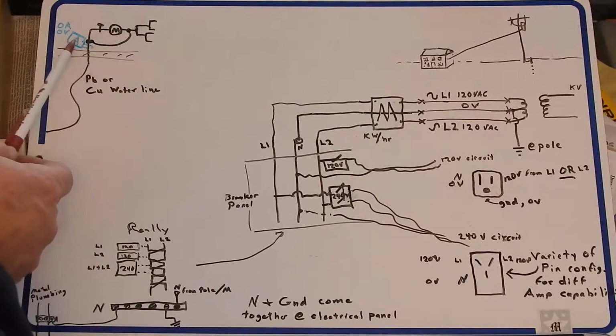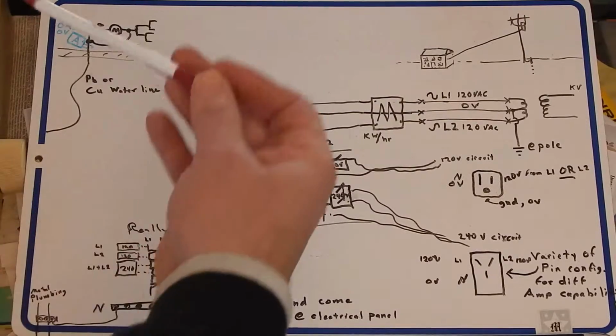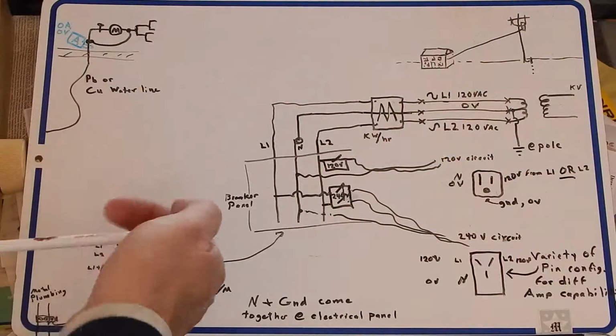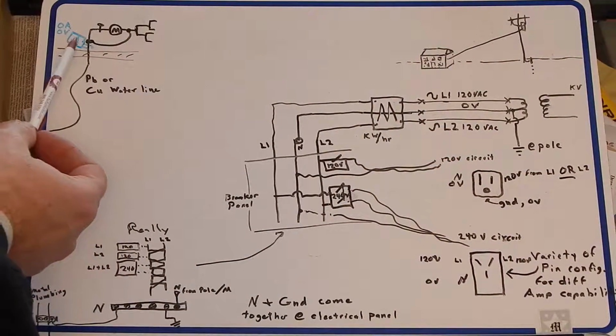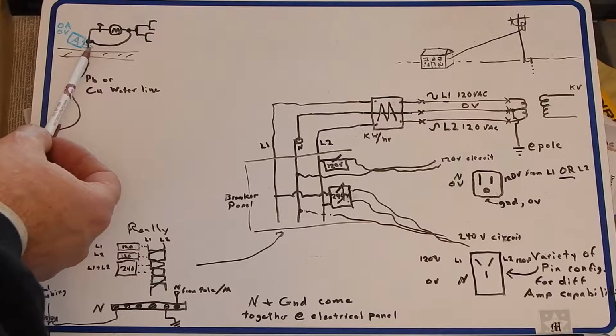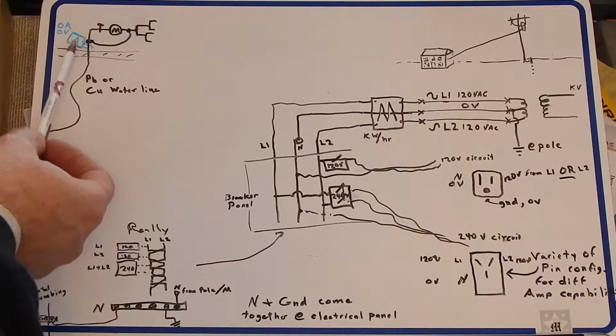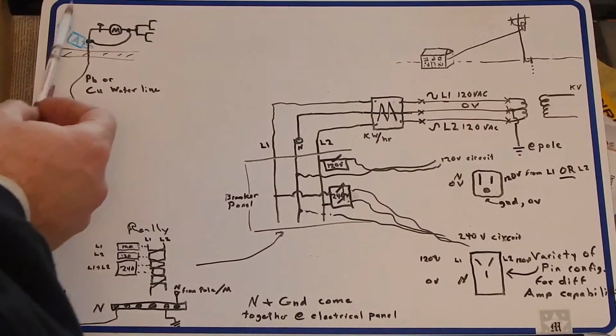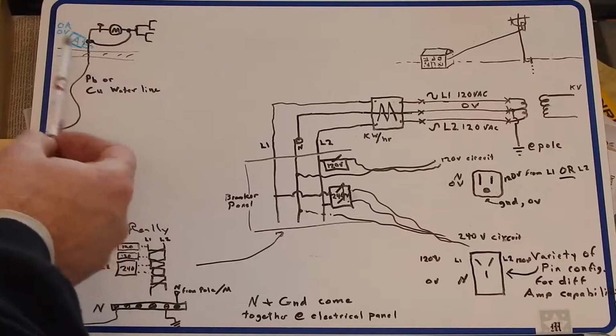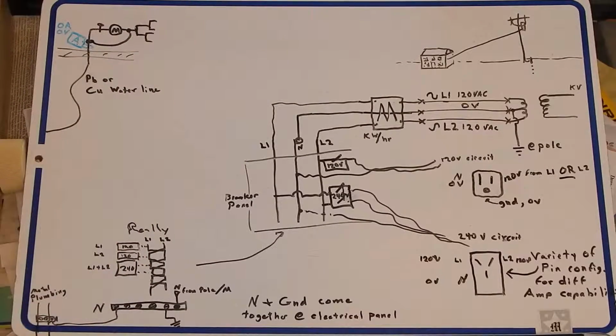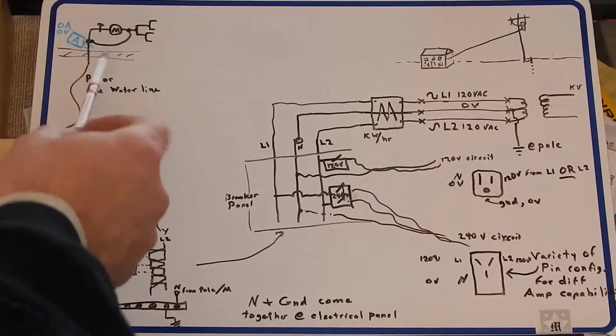Ideally, if you put an amp meter, one of the clamp amp meters, which will encircle something as big as a pipe, a typical clamp meter will do that, go right around the water pipe. You should have very low current there. I have 0 amps, and if you used a volt probe to ground, you should get 0 volts. You know, that's ideal. You're always going to have some amperage and some current, some voltage, but you want that as low as you can.